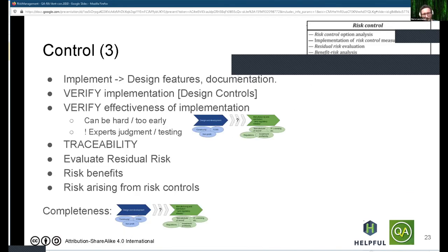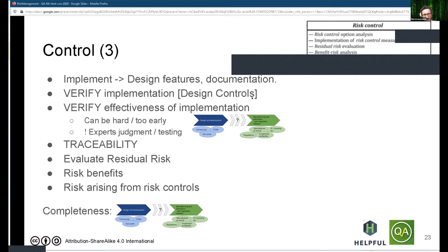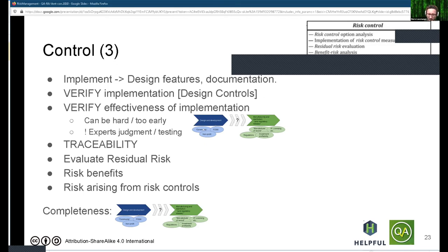Implementing those risk controls means different design features and sometimes documentation. All of these need to be verified for implementation and for effectiveness — one of the next speakers will be talking about design controls and how to do that. There can be a lot of expert judgment as well as testing involved. You want to be traceable, so you need a means of keeping traceability between your hazards, your risk controls, and the design features that implement them.